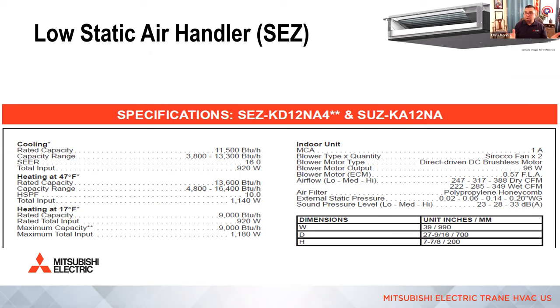So this is the submittal, just the top portion of the submittal. And you can see on the right-hand side, I just have to move my video, I apologize. On the right-hand side, you can see we actually list the ECM motor amperage. We also give you airflow on low, medium, and high with a dry coil and a wet coil. And then of course your external static pressure.